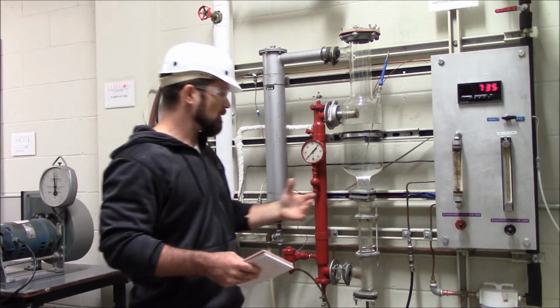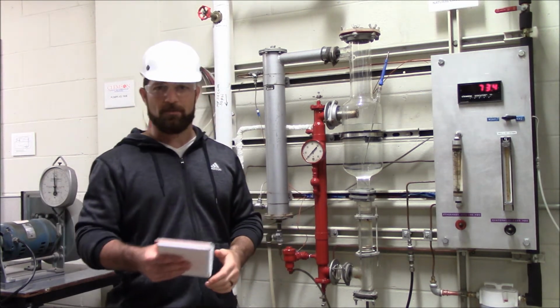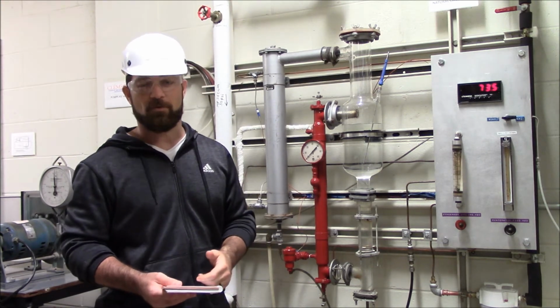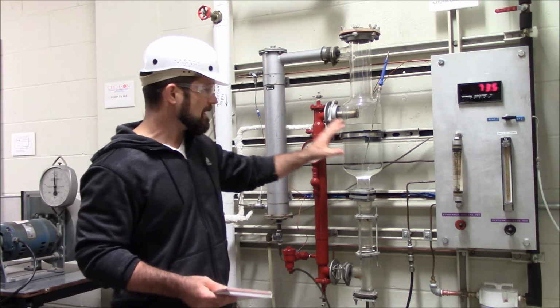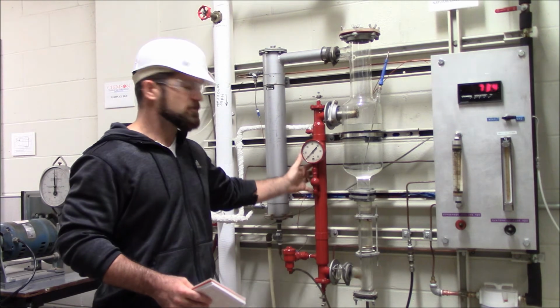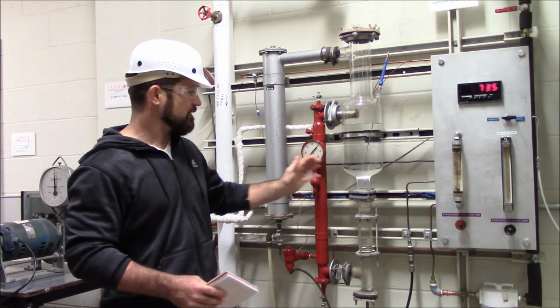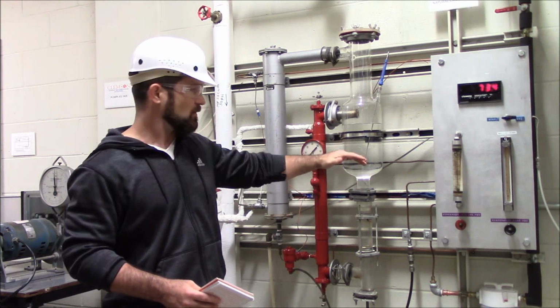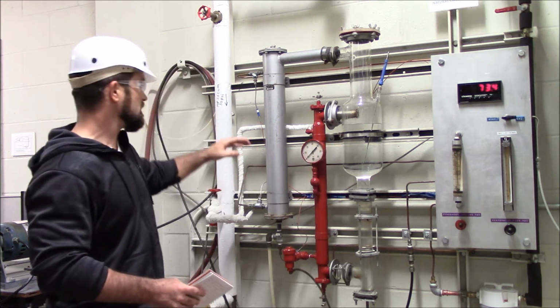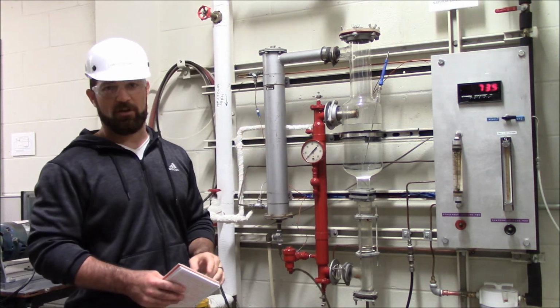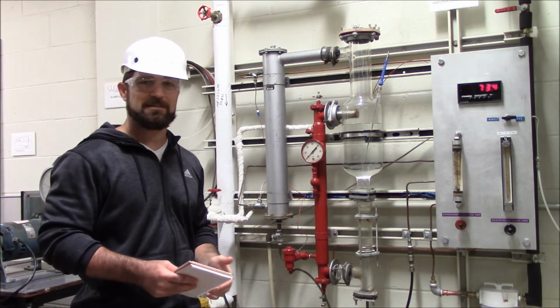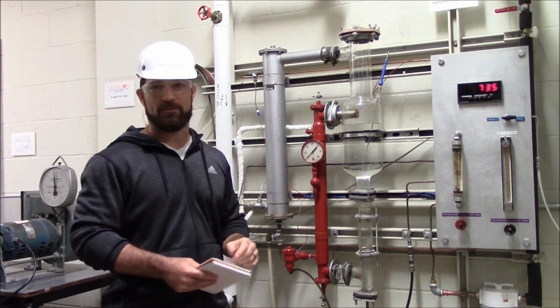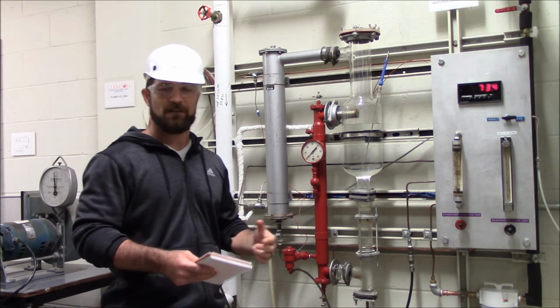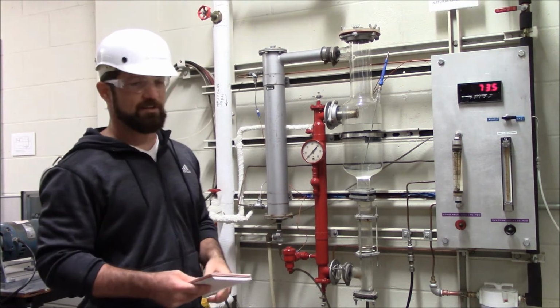Okay, so now when we're getting ready to run this, the order in which you do things is important. First of all, the main thing you want to think about is absolutely do not turn on the steam if there is no liquid in your evaporator and if the cooling water to the condenser is not turned on. That's the most important thing about this particular experiment. Otherwise, it's fairly safe, fairly easy, fairly routine.